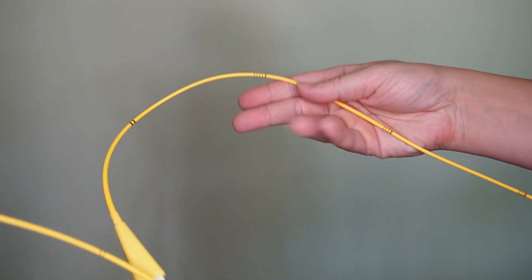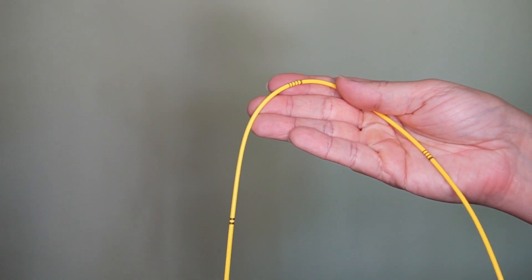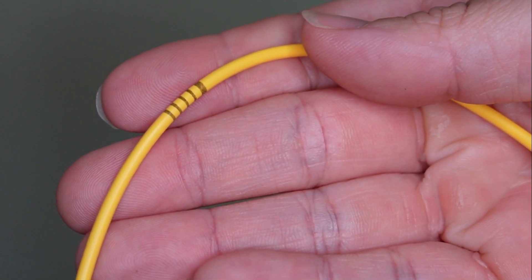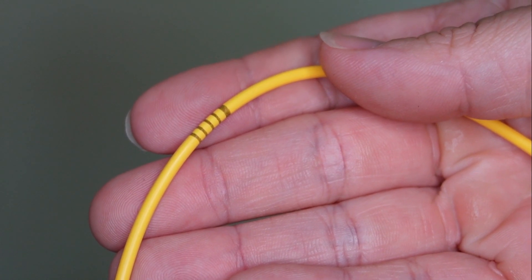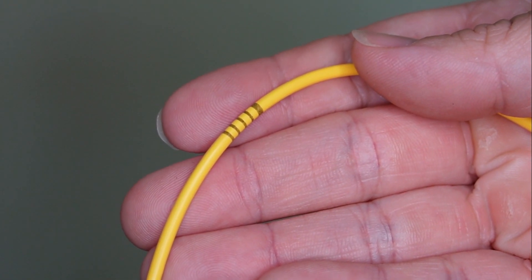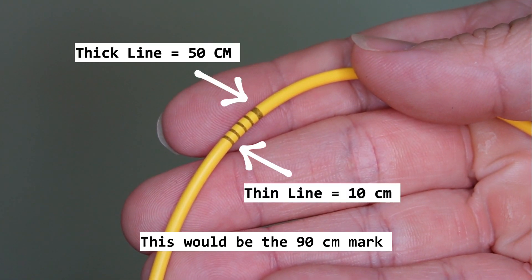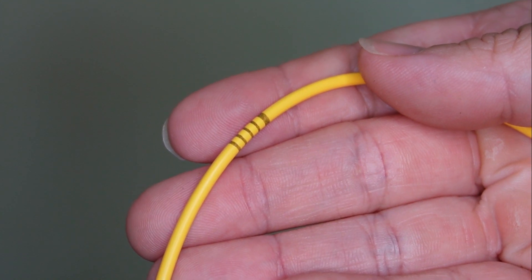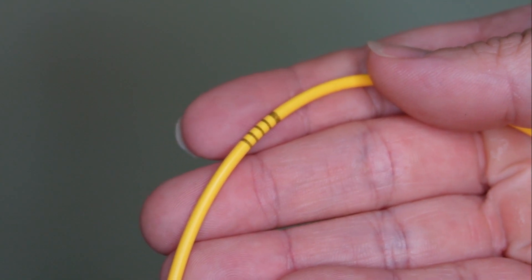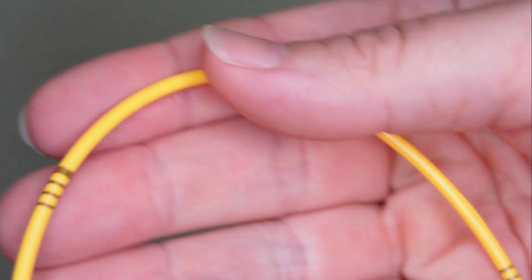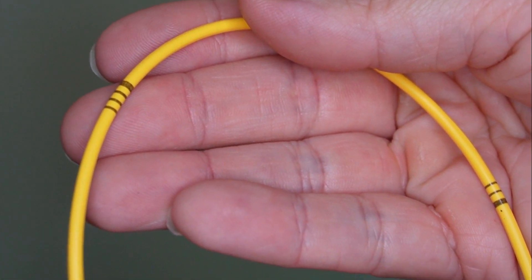Each catheter will have thick lines and thin lines. These lines represent centimeter markings and will assist with knowing where the catheter position is. A thick line represents 50 centimeters and a thin line represents 10 centimeters. You want to measure the estimated centimeter marking at the level of the cordis, introducer, or sheath. You must know the centimeter marker of the catheter because it allows you to assess if the catheter has moved or is out of position.